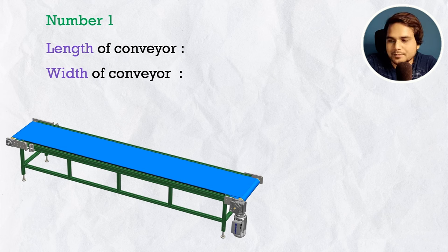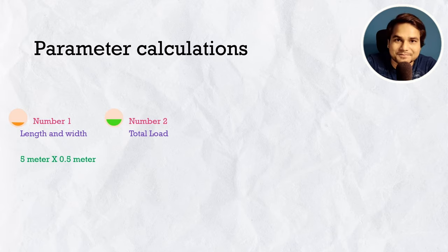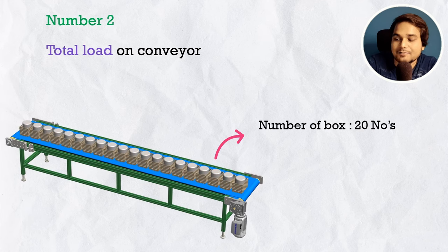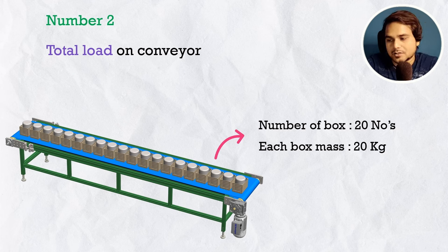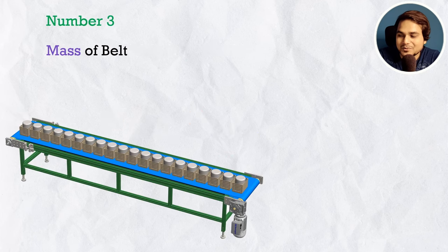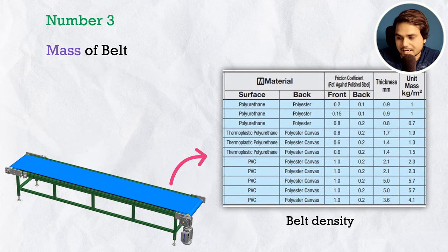To calculate the required motor power, we need several parameters. Number one: total length and width of the belt conveyor — for example, length 5 meters, width 500 mm. Number two: load over the conveyor belt — for example, 20 boxes each 20 kg, so total load mass is 400 kg. Number three: total mass of the belt, calculated using the selected belt material density for the given belt size.